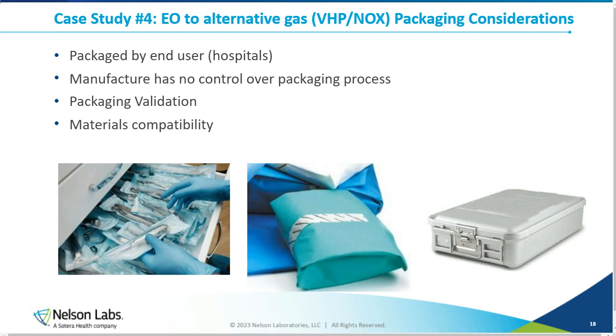So if you were going to go this route, produce this in a large amount, and sell it as non-sterile, you should consider how the hospital is going to package it for sterilization on site. Make sure that it's compatible, not just with the type of sterilization, such as VHP or Noxilizer, but that the packaging they would select, and the sterile barrier system they're likely to use, can handle the sterilization cycle. The hospital isn't going to do a validation to make sure that sterilization cycle will work with your product, so you would really want to cover that yourself.